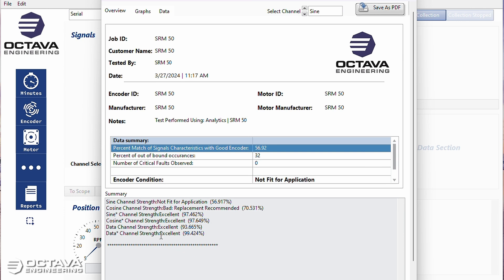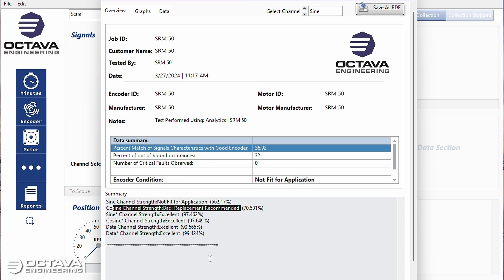And if you see here, it's primarily because of the sine channel and the cosine channel. So the signal strengths on the nots, again, sine not and cosine not for SICK hyperface is just a reference voltage, a flat reference voltage. And then the data and data not channels, those signal strengths were fine.